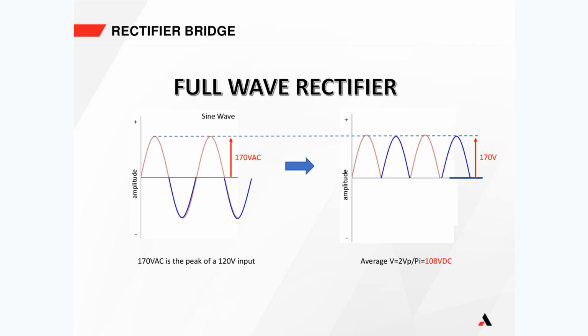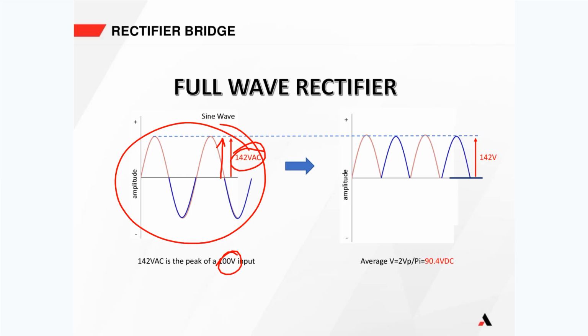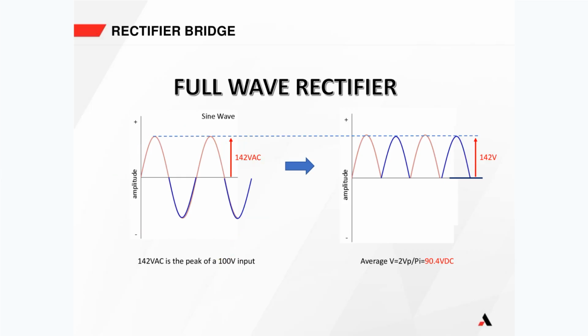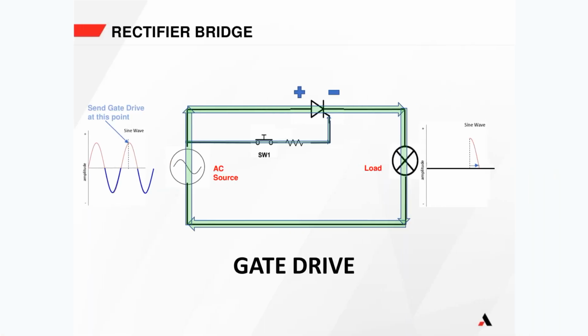So follow me with this. If the RMS value goes down, from 120 to 100 volts, the peak of the waveform now goes down to 142 rather than 170. So the average has gone down to 90.4 volts, and we would, in theory, be undercharging the batteries. If it went up, we would be overcharging the batteries.